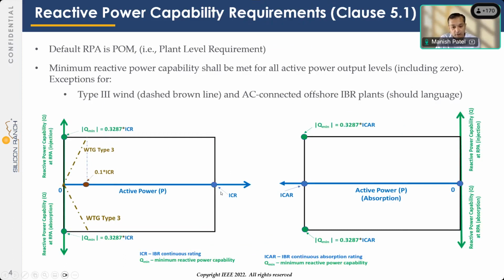ICR is the IBR continuous rating, so if it's a 100 megawatt plant, then ICR is 100 megawatt. What this means is that for any active power between 0 and ICR, the plant is required to be able to absorb and inject 33% of ICR as reactive power. So x-axis is megawatts or active power, y-axis is reactive power.